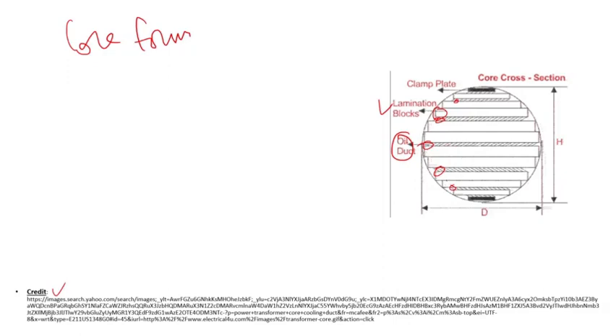Because you have these cooling ducts, each section would have a core ground, like a strap or a jumper basically. It doesn't matter where you put it, as long as it's between sections. For instance, in this example, this is one section, and you do the same thing for the other ones. But what I was saying was, some manufacturers will put just one jumper. So this is the core ground, which would go to a bushing, and then that bushing would be grounded. What they would do is insert a jumper between these two here. Some people put some kind of conductor in between, and that way you bridge those two sections, and in that case you only need one core ground.